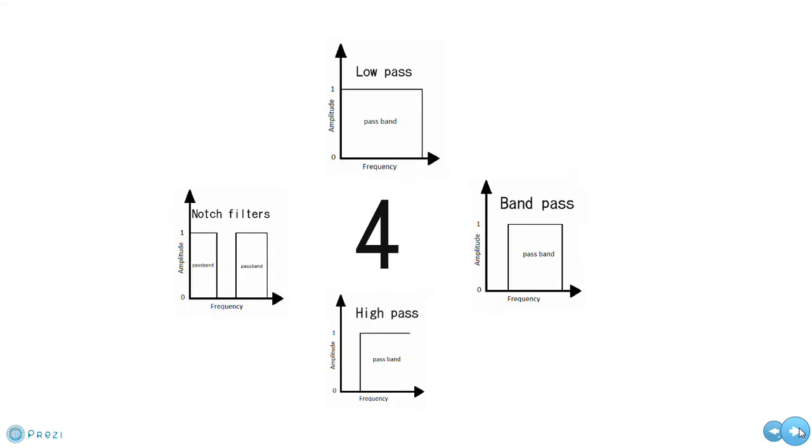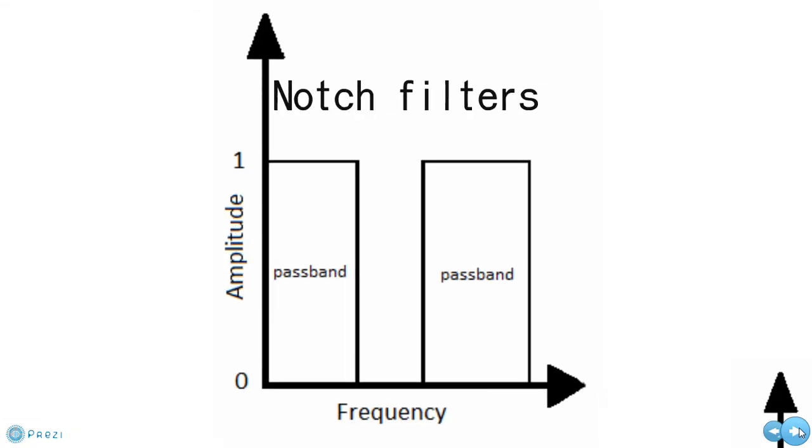And finally, there are notch filters that remove particular frequencies from the signals. For example, they remove the 50 and 60 hertz mains interference that can be experienced when making muscle and nerve recordings. They are rarely used as they can distort the signal of interest and have been superseded by differential amplifiers.